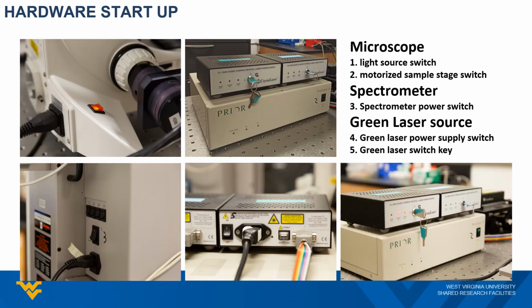Now let us go through the system startup procedure. For the microscope, you will need to turn on the microscope illumination source and the control box for the motorized sample stage. For the spectrometer, you will need to turn on the main switch from the back of the machine. And for the green laser source, you will need to turn on the power supply box from the back, then rotate the key at the front to activate the laser.